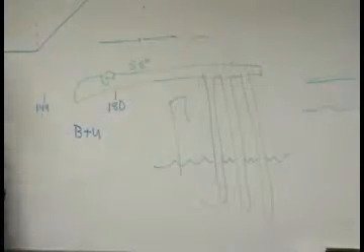This whole thing I'm talking about is a closed loop. You'll keep it in a closed loop. I have seen, I don't know if they do it anymore, years ago, if you were in the country and you had a well, you could just suck the old water out of the ground, run it through your heat pump, and then dump it somewhere, in the creek in the backyard, or water your lawn with it. Again, you get to use that nice 50-some degree water coming out of the ground. That's the most efficient way, because with the closed loop, the loop is always heating or cooling the ground, while with the open loop, it's not. With this, you're using that temperature once and then chucking it.